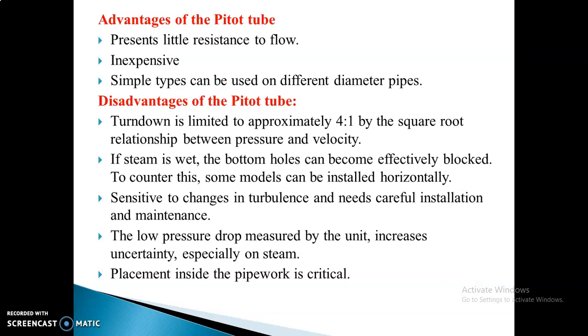So automatically the diaphragm will identify the differential pressure head based on these 2 points, that is your pressure drop point as well as the stagnation pressure. So automatically it can measure the pressure value. So using that pressure value, we can calibrate it in terms of flow of liquid, in which we can calculate the flow rate of the liquid. That is how your Pitot tube is working.